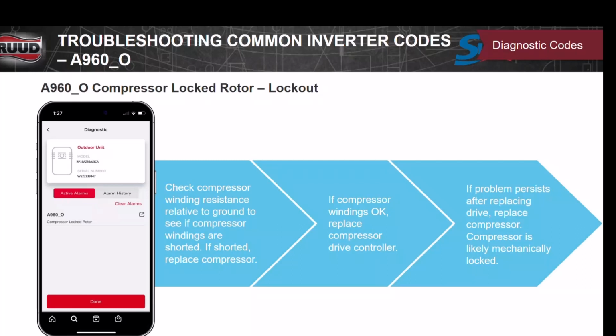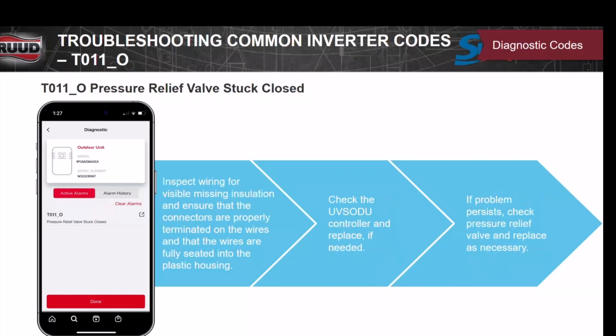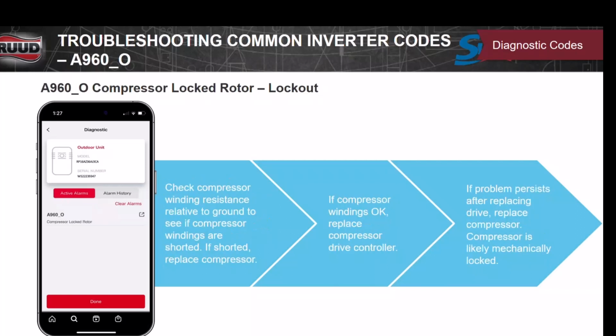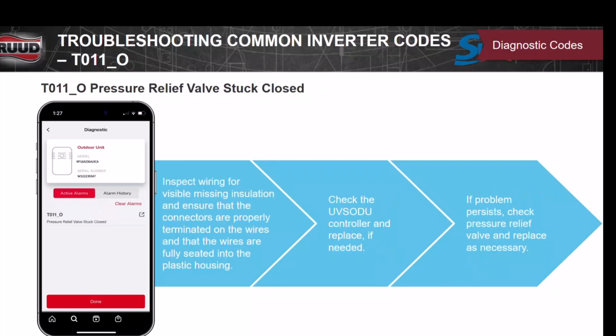If all the readings out there are okay, if you don't see anything with the compressor, then we're going to look at replacing a board, the inverter board, possibly. But when I say I've seen this, this is on a true variable speed compressor, where I've seen it grounded one of the legs. Normally, when you have a leg grounded, it's going to short out, right? But it goes through that inverter, and that inverter is pushing that voltage through, and this still was grounded.